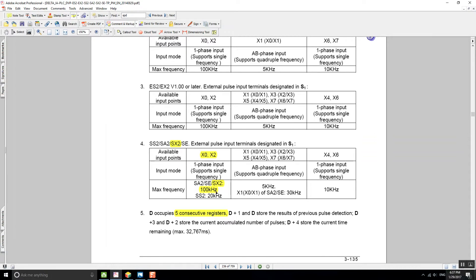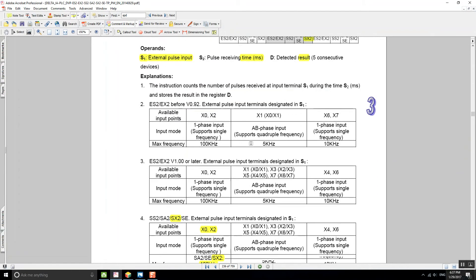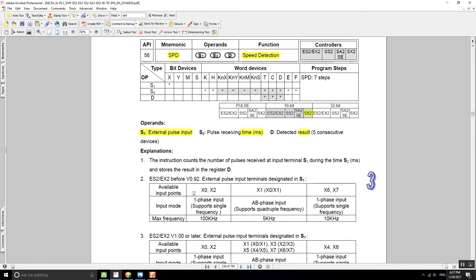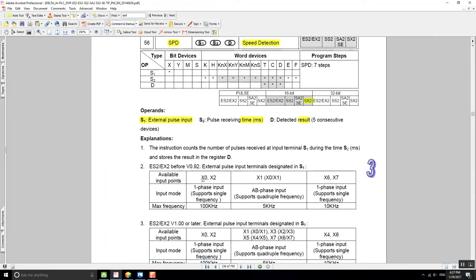For the other inputs X1, X3, X5, and X7, using the AB phase input (two wires going in), we can go up to 5 kilohertz. For inputs X4 and X6 with just one-phase input, we can also go up to 10 kilohertz for this model. You should check your model to see what inputs are available for your PLC.